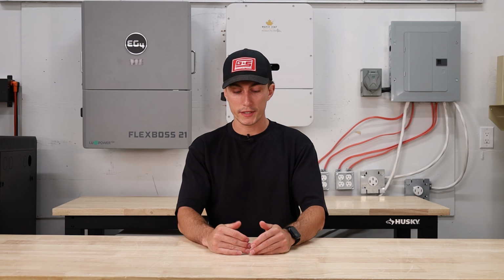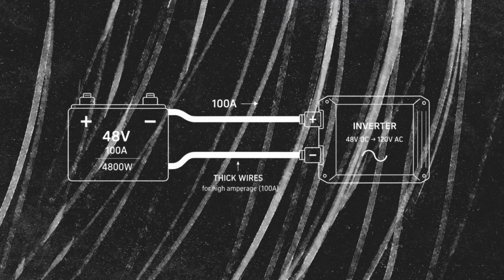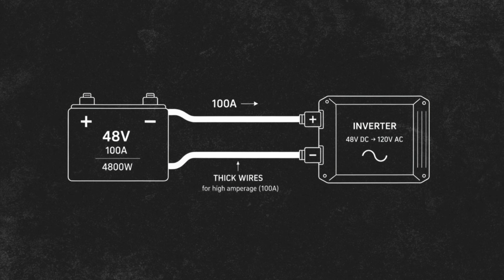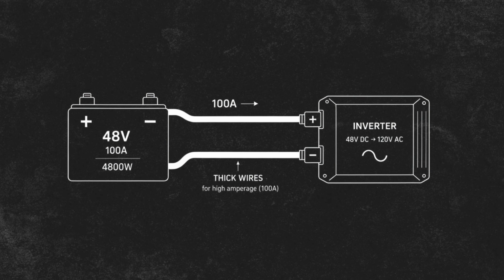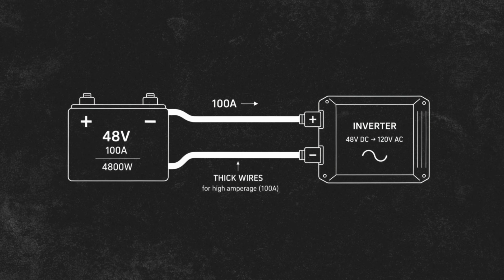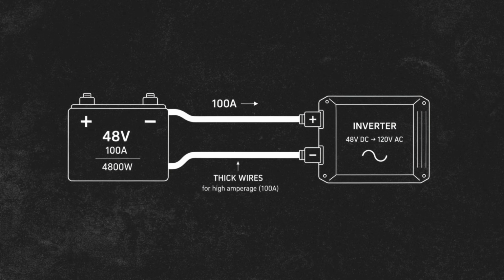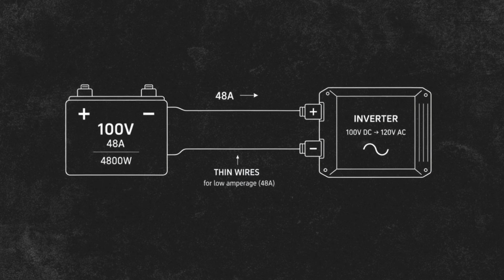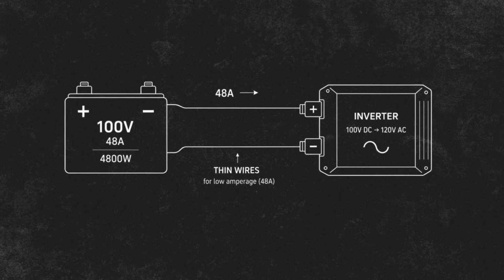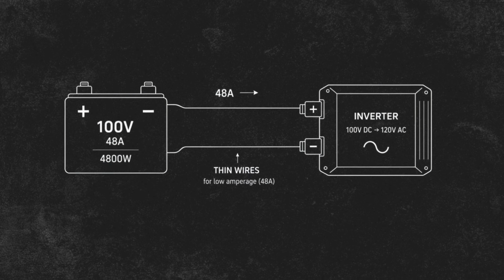With a 48 volt system, to deliver the same power as a high voltage system, your current is about 4 to 8 times higher to get the same output. In simple words, because the voltage is lower, you need higher amperage to move the same power through your wires. So if you had a 48 volt battery running at 100 amps, you'd get 4,800 watts. To get that same 4,800 watts from a system running 100 volts, you only need 48 amps. So you basically need half the gauge of wire to get the same amount of power through your system.